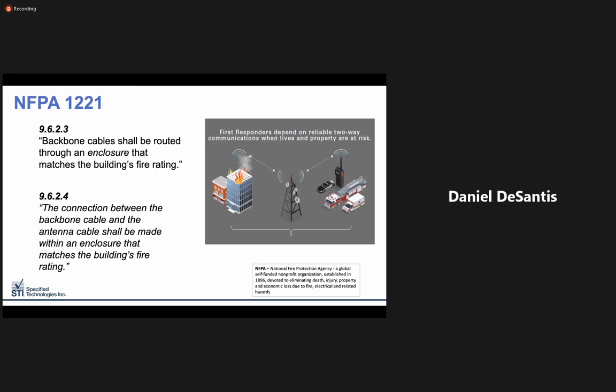The standard's next mention of rated enclosures is in the following chapter. The connection between the backbone cables and the antenna cable shall be made within an enclosure that matches the building's rating. This refers to the connection between the vertical backbone cable and the horizontal antenna offsets, which should be made inside an enclosure that matches the building's rating, typically 2 hours in most cases.